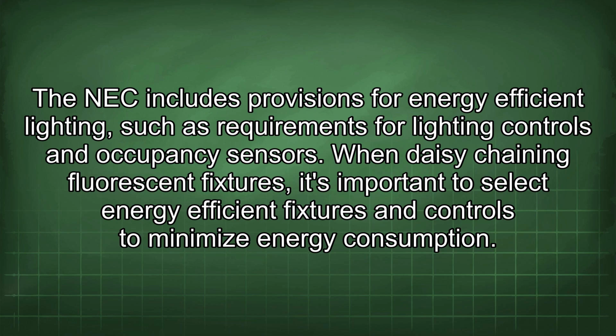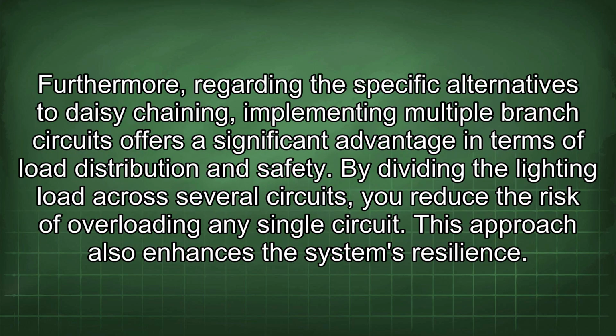When daisy-chaining fluorescent fixtures, it's important to select energy-efficient fixtures and controls to minimize energy consumption. Furthermore, regarding the specific alternatives to daisy-chaining, implementing multiple branch circuits offers a significant advantage in terms of load distribution and safety. By dividing the lighting load across several circuits, you reduce the risk of overloading any single circuit. This approach also enhances the system's resilience.